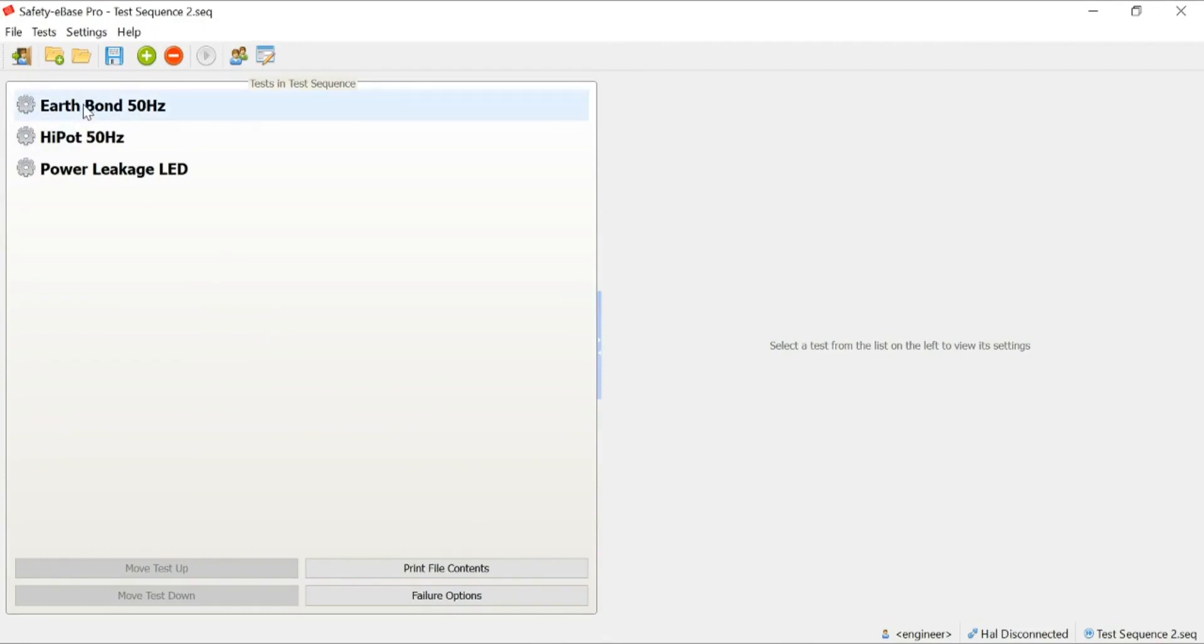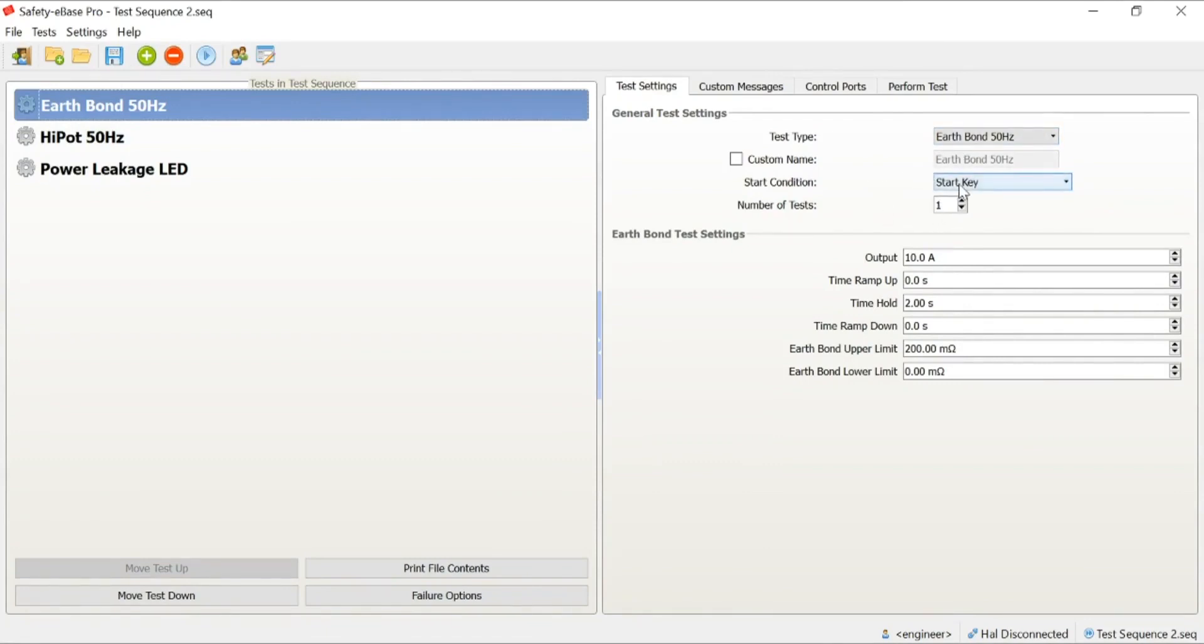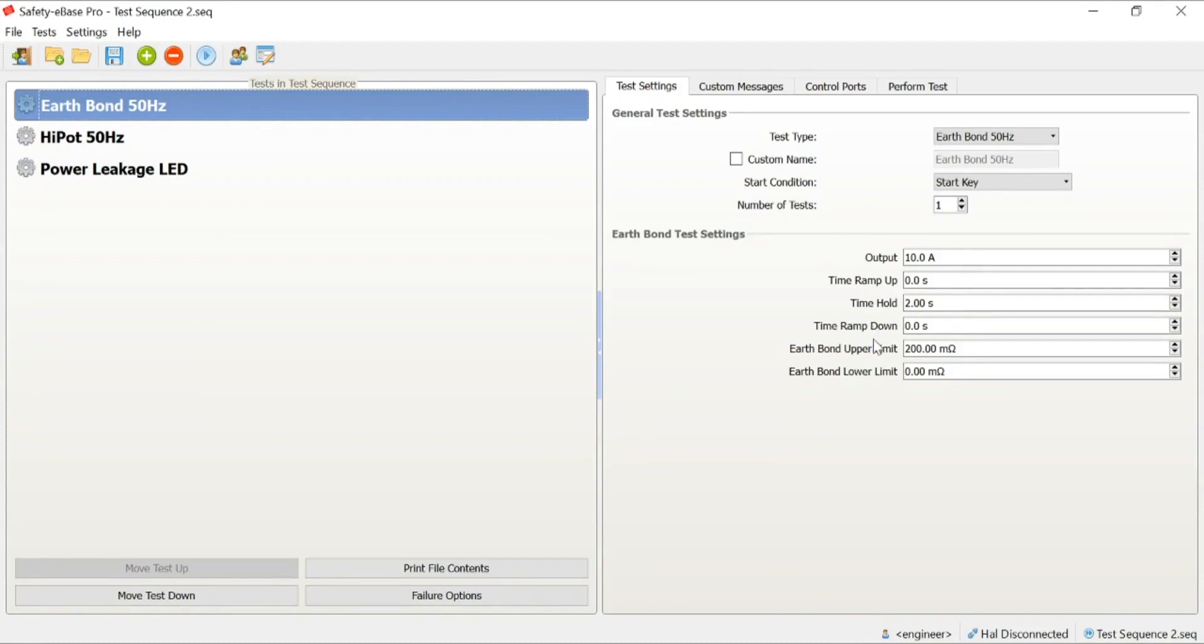Firstly, you'll see we have our EarthBond test. When we click on the test, whether it's new or an existing one, we start to see all of the test sequence settings being displayed over in the right-hand side. At this point, we can do everything that we could have done on the HAL. You can see we can choose the test type we want to perform, we can define a start condition, we can decide how many times we want to perform the test, and then we can set our test parameters up. What our output needs to be, how long the test should be performed, our ramp up, hold, and ramp down times, as well as our upper and lower limits.